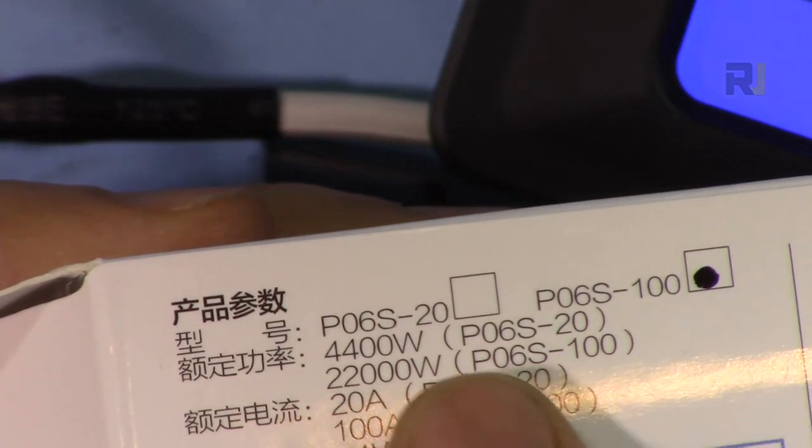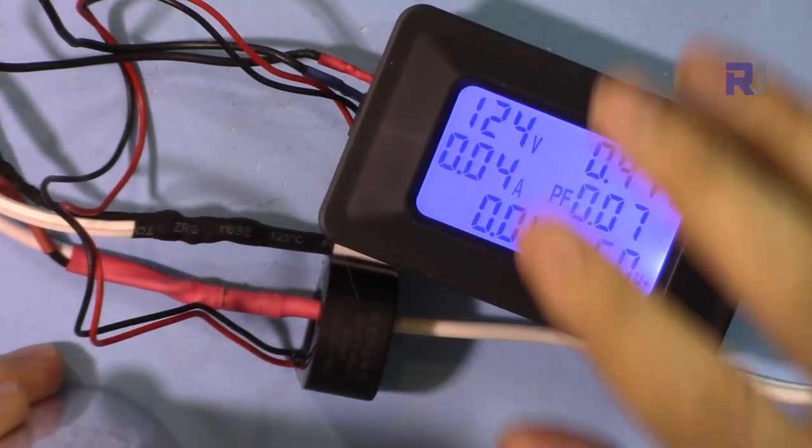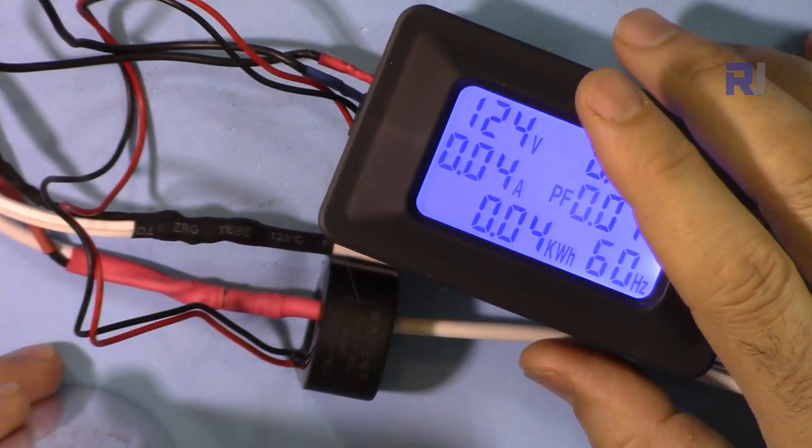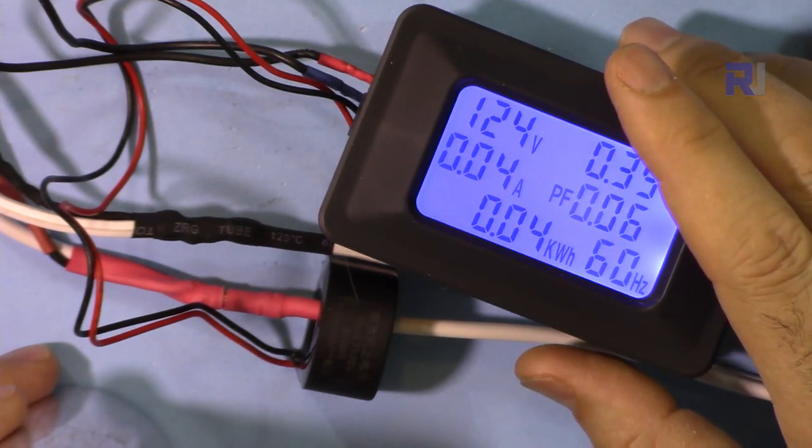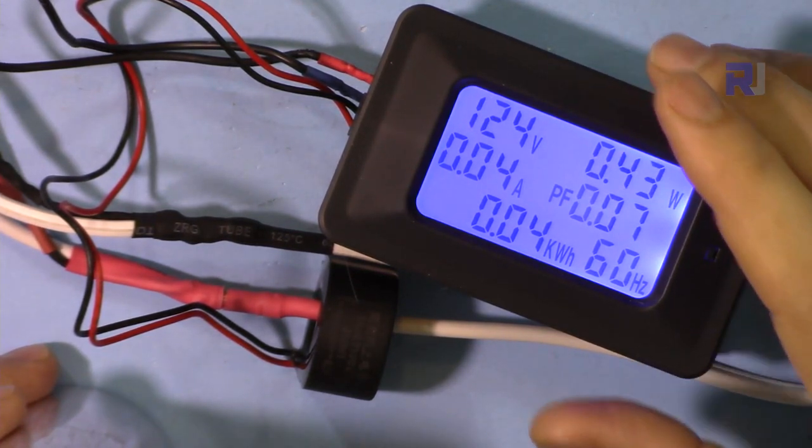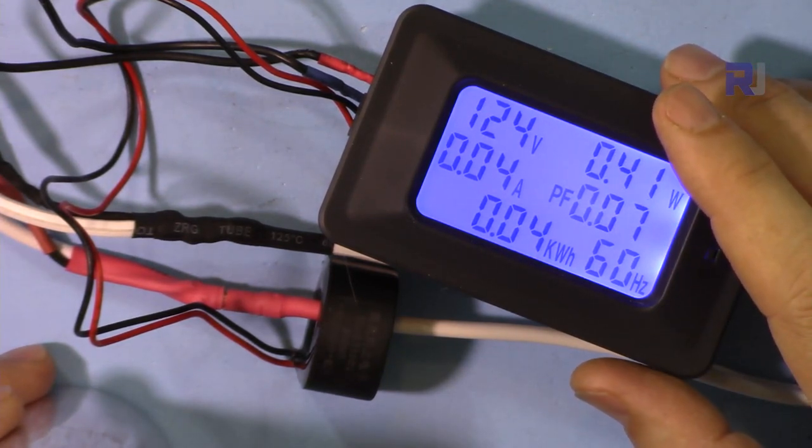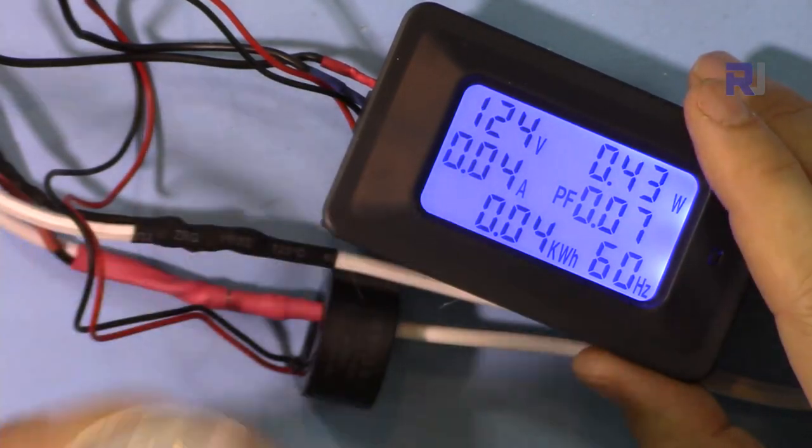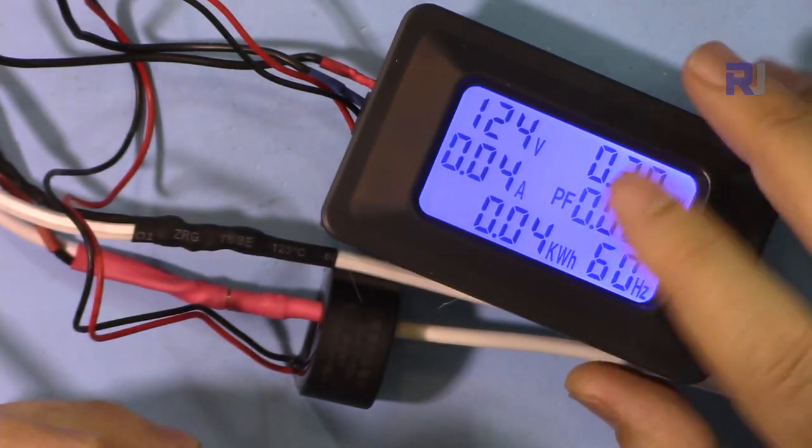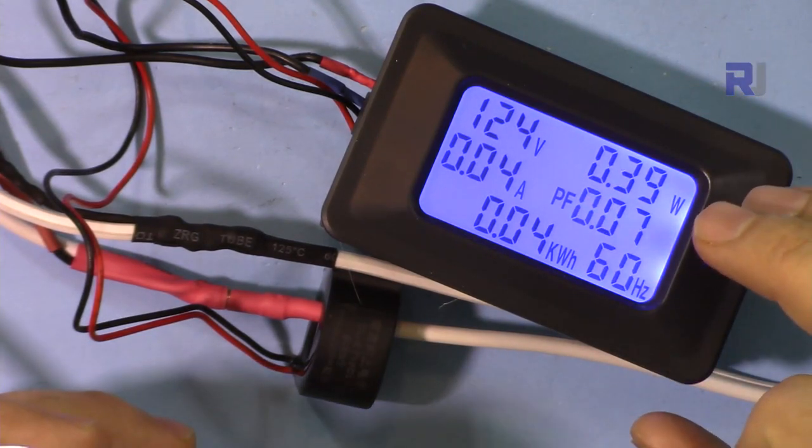The model for this one is P06S-100, this is a 100 ampere version, and there's also a P06S-20 which is 20 ampere version. I'm going to measure two different devices. One is pure resistive load, a toaster, and also a heat gun which has a motor inductive load and the heating element which is resistive. Then I'm going to connect a capacitor in parallel with the load to see the reactive load and how this one handles it.